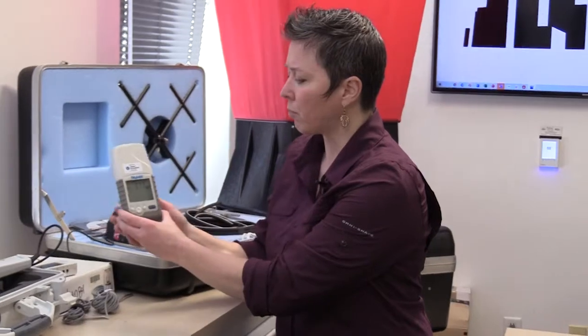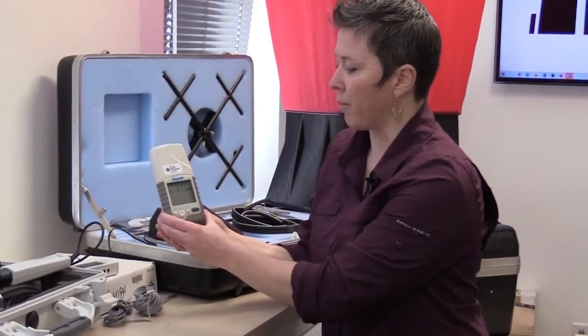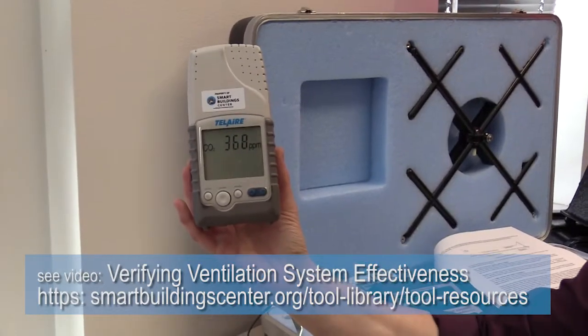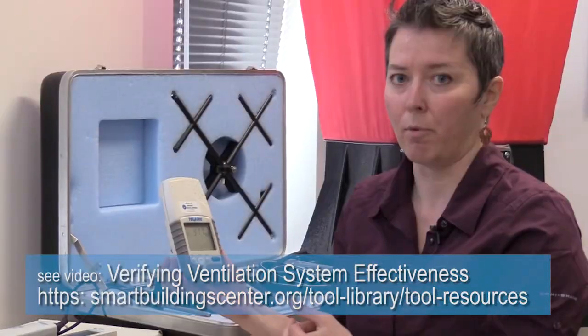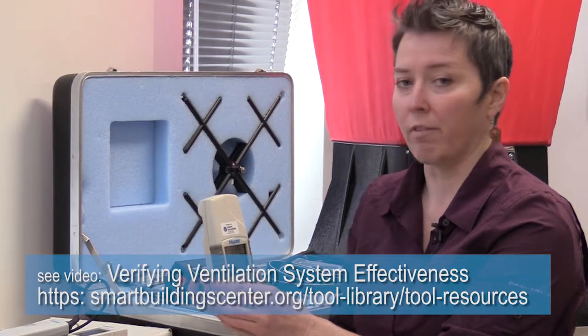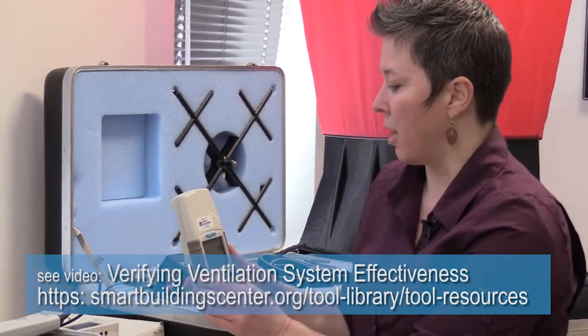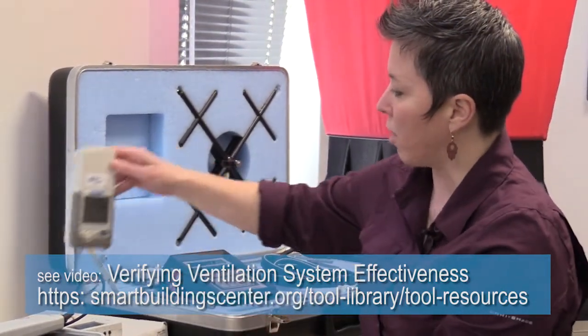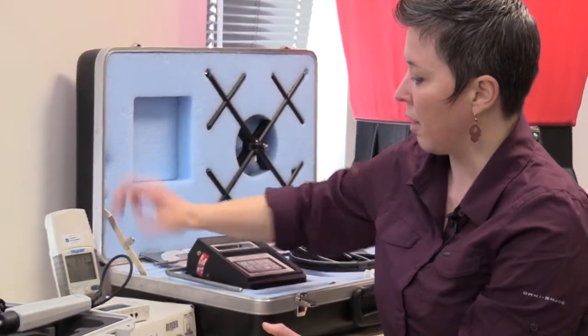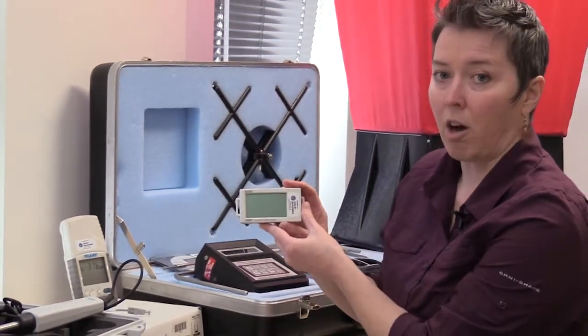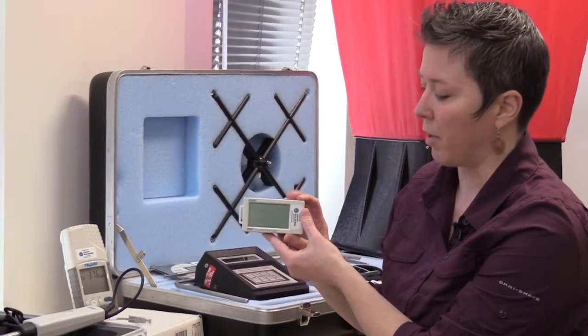So we have this Telaire CO2 monitor, and we actually have another video you can check out that goes into detail about how to set up and operate this to measure your ventilation system effectiveness. But essentially this plugs into a Hobo data logger, and there are several that can work for this application.